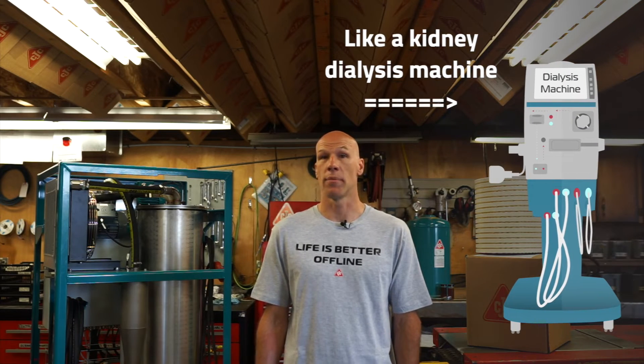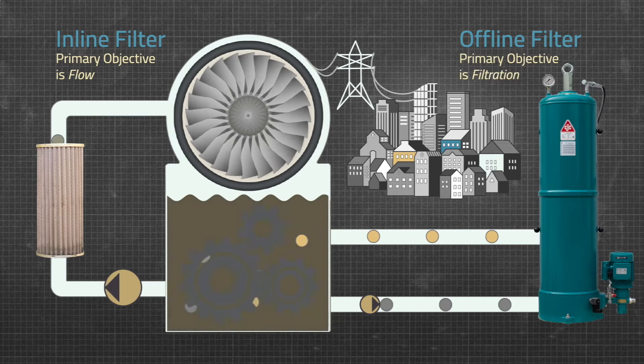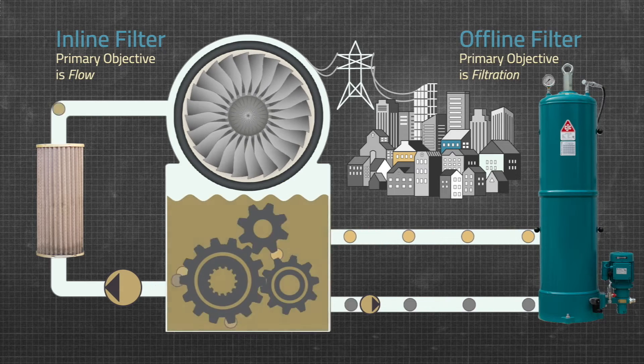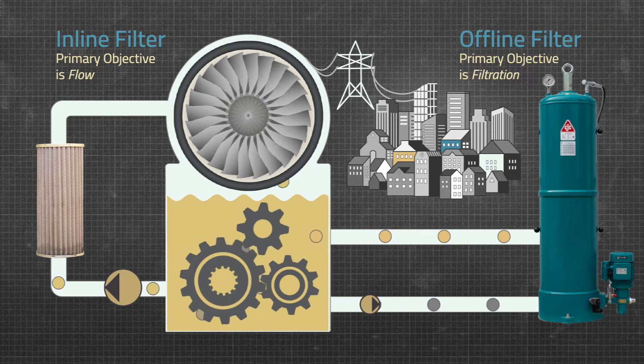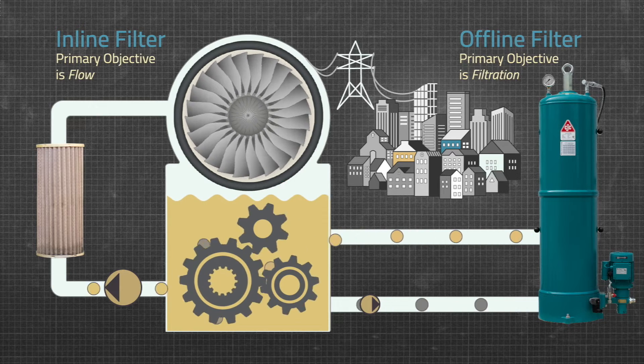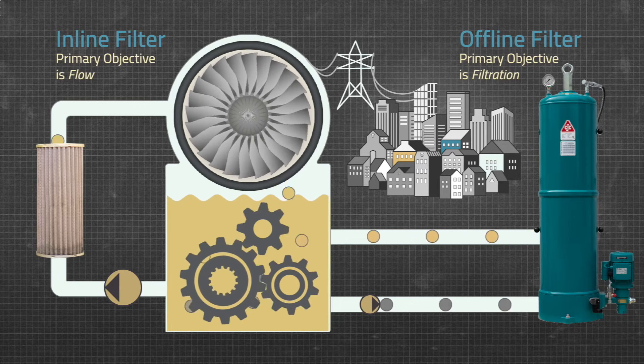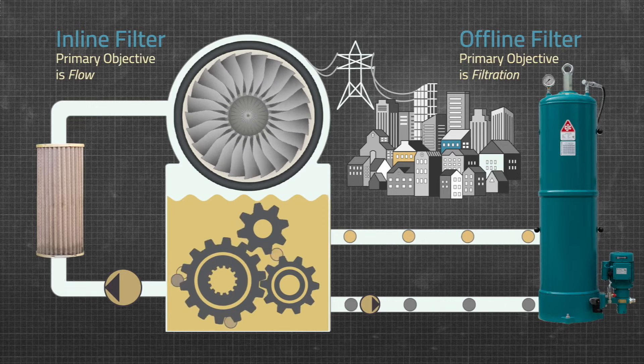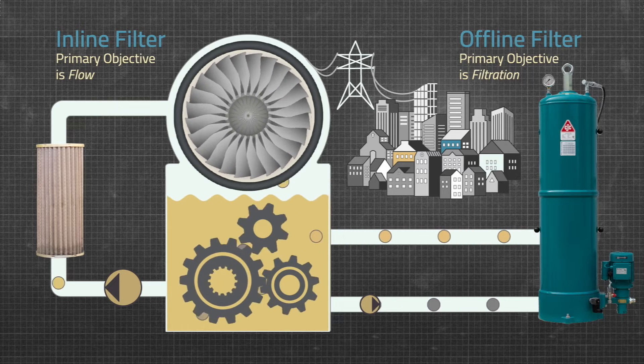But trying to filter ultrafine at high flow comes at the expense of restriction, or rapid filter consumption, or both. Unlike inline filters, offline filters operate in their own slipstream loop outside the main system, leaving that critical flow rate unaffected. The primary mission of the offline filtration is filtration. Because this filter is located in a completely different circuit, flow rate can be optimized to remove problematic contaminants from the oil.